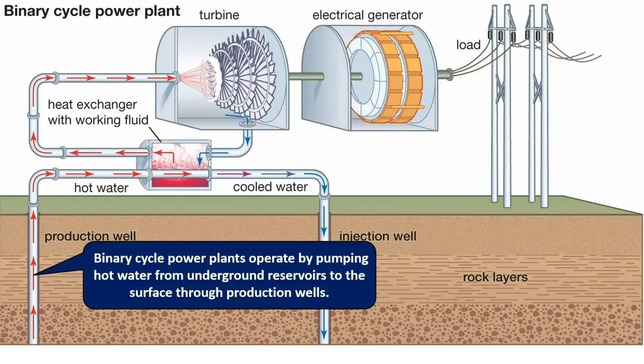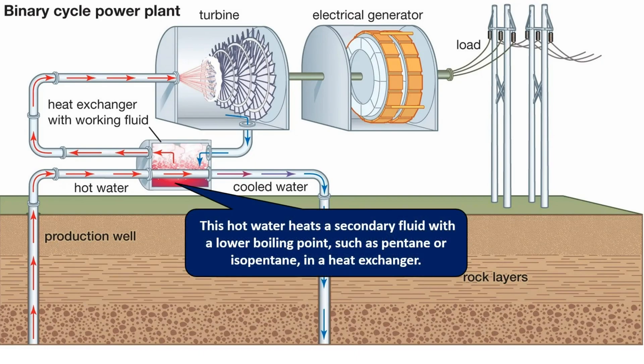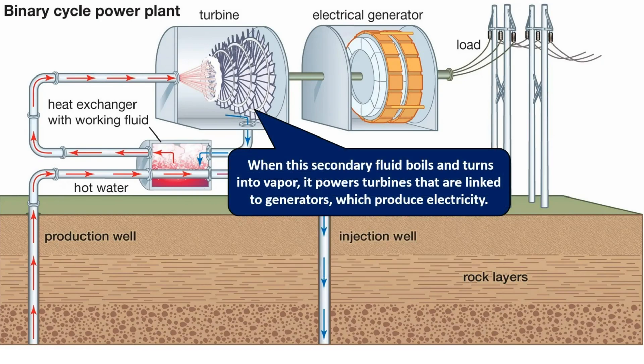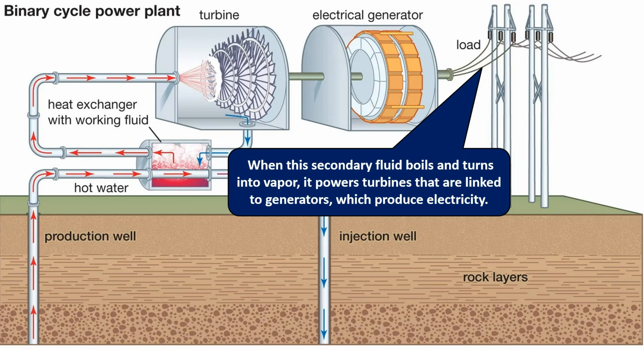Binary cycle power plants operate by pumping hot water from underground reservoirs to the surface through production wells. This hot water heats a secondary fluid with a lower boiling point, such as pentane or isopentane, in a heat exchanger. When this secondary fluid boils and turns into vapor, it powers turbines that are linked to generators, which produce electricity.